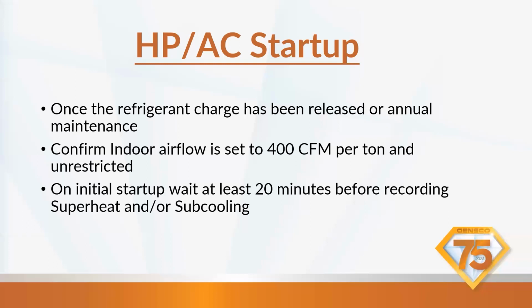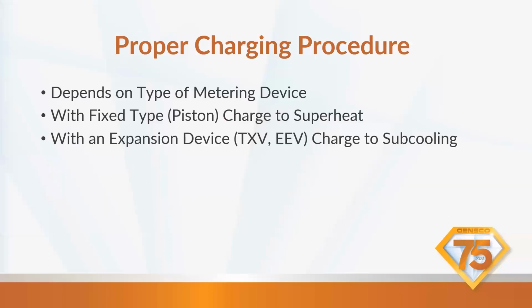On initial startup, you're going to wait at least 20 minutes before recording superheat and subcool. If it's been in an idle state, the system needs to run and get that refrigerant moving through, and it takes at least 20 minutes before you can start gathering your refrigerant readings. So start it up and start doing something else. Your proper charging procedure depends on what type of metering device you have. Is it a fixed piston type to charge the superheat? So that's going to be AC. I guess we do have some heat pumps out there with piston too.